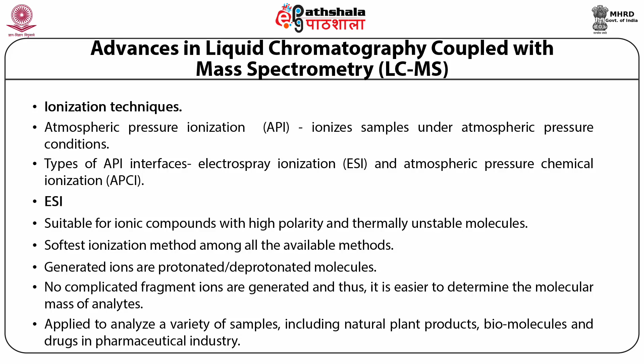APCI is a chemical ionization method. Its interface is designed in such a way that it is similar to ESI, but its ionization principle is different. This method is mainly suitable for analytes with low or medium polarity. In this method, solvent and sample molecules are vaporized by spraying the sample solution into a 400 degree centigrade heater. For spraying, a gas source such as N2 is used.